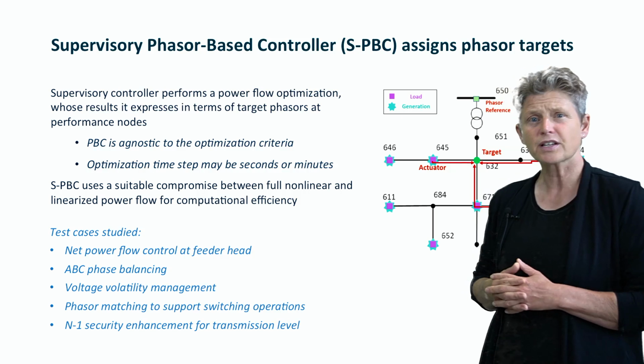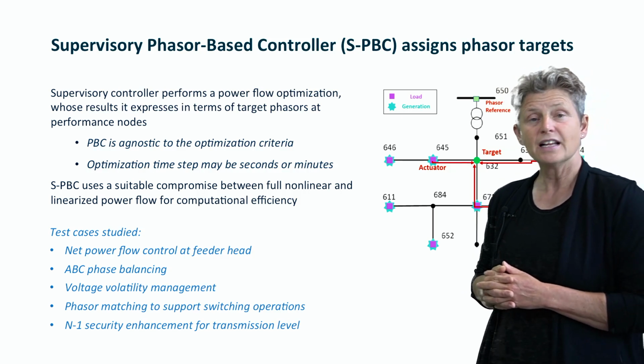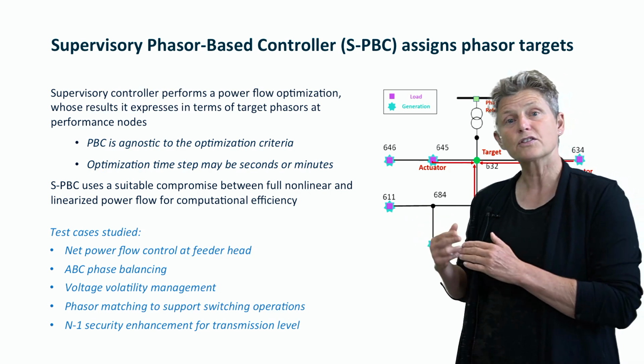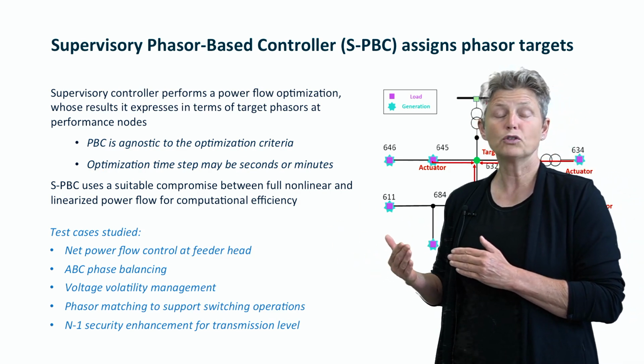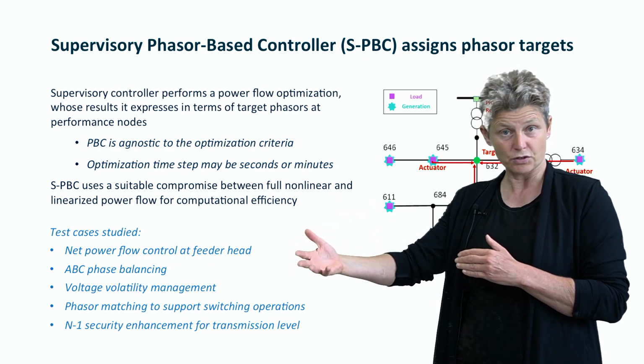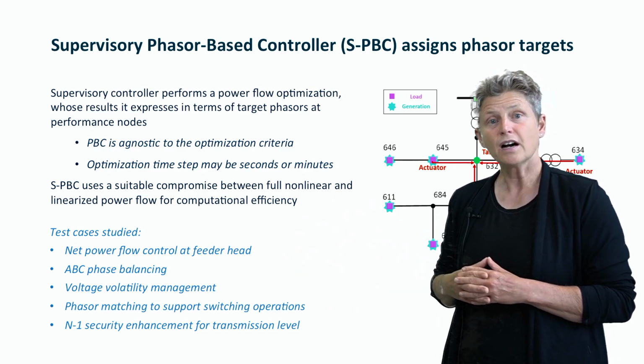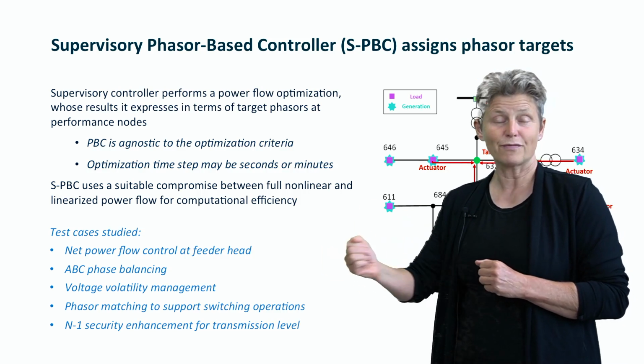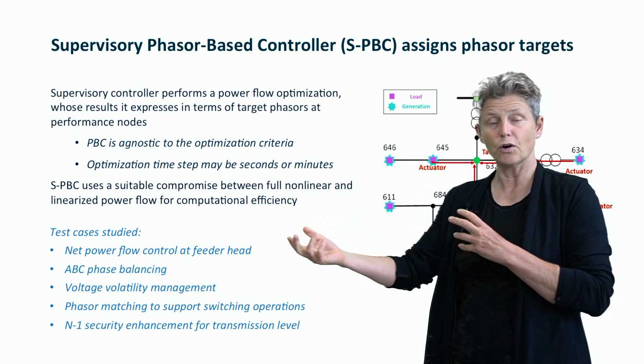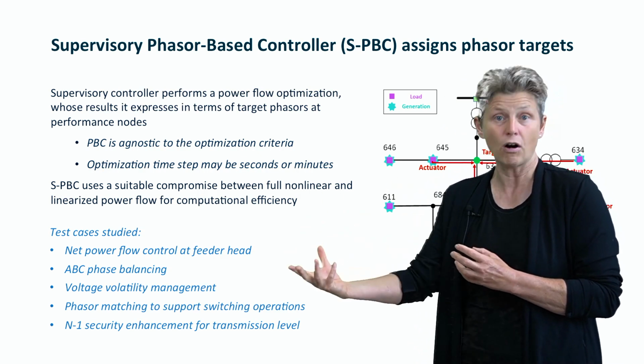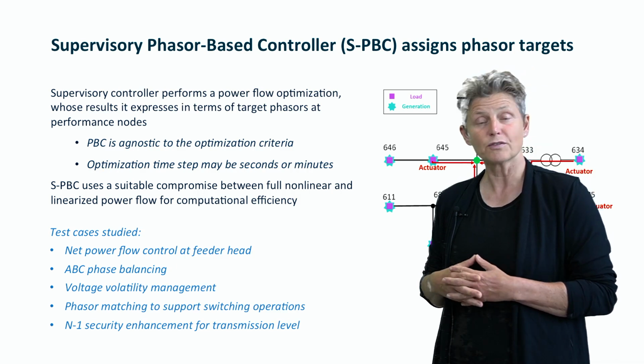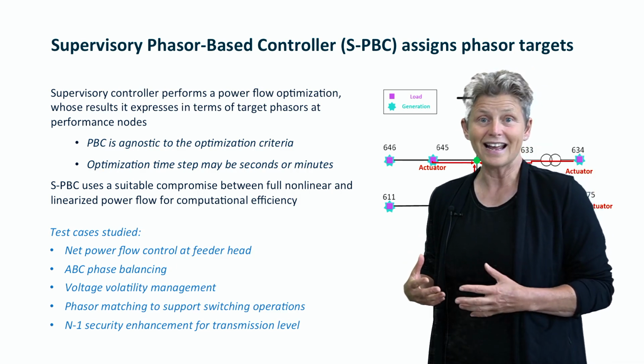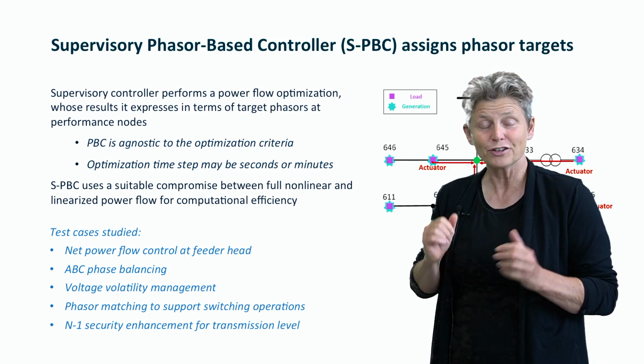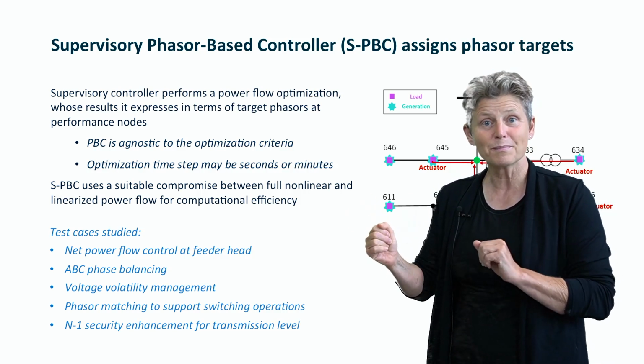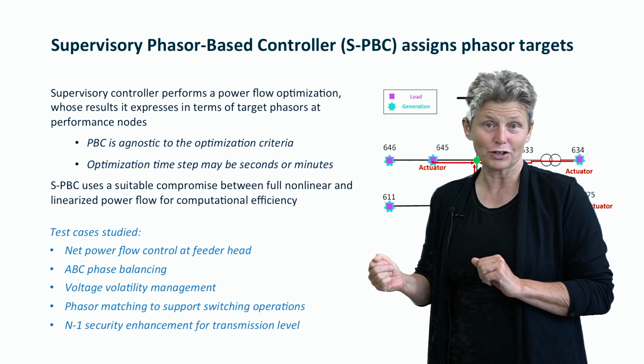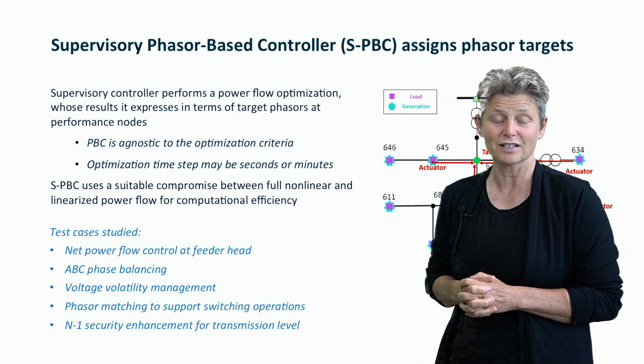Another interesting use case would be to drive the phasor to a particular value at a point on one side of an open switch between this circuit and a neighboring circuit or circuit section. Because when you're about to close a physical switch, you want to make sure the voltages on the two sides are not too different - otherwise you get a big arc across the switch. Sometimes in real life, utilities would actually bring a diesel genset out to location to help drive the phasors to make them compatible, to close a switch without previously having to de-energize everything.